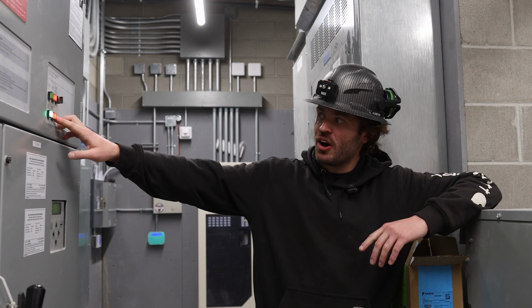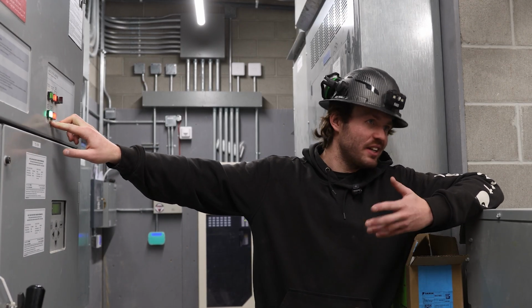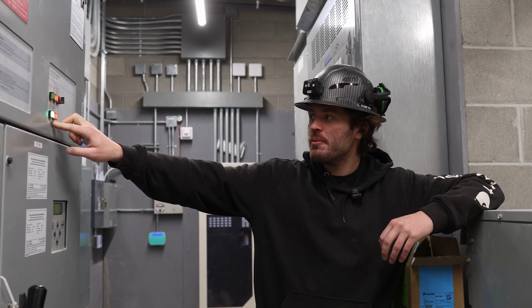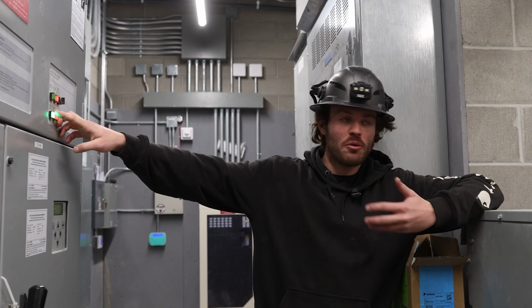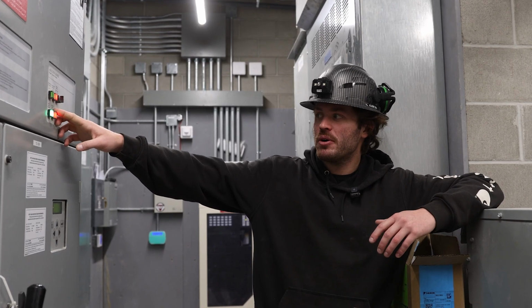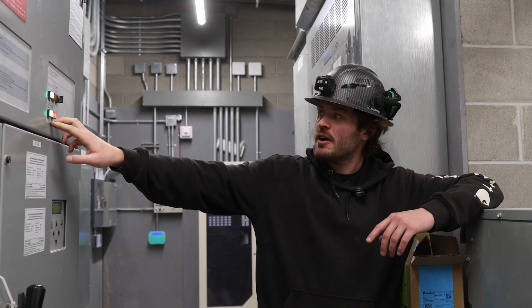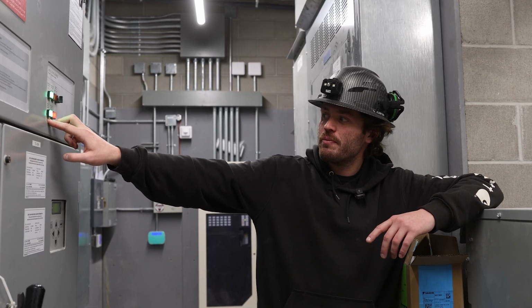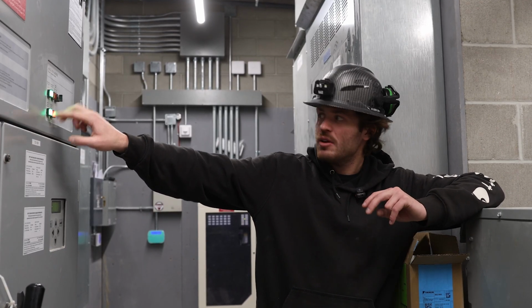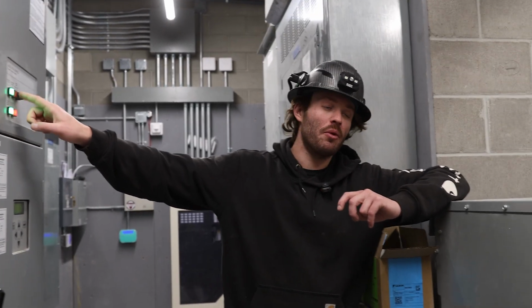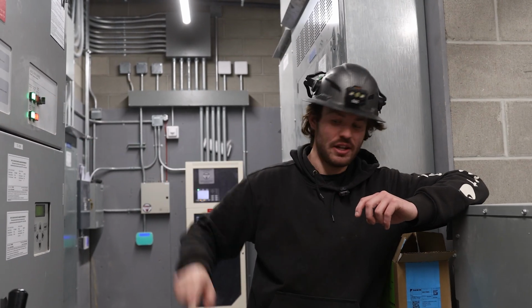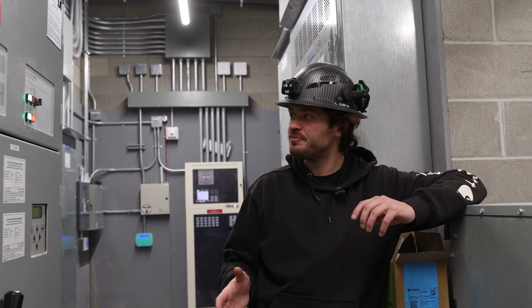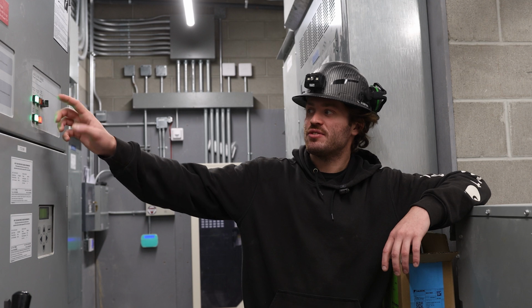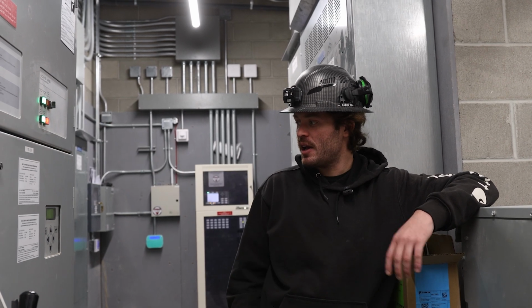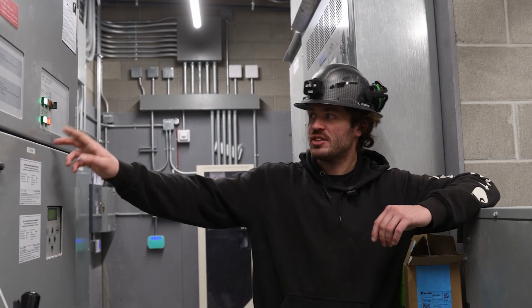The lights up at the top are a quick indication of what's going on. The green ones are normal power, red ones are emergency power. The bottom two show if the source is good. Of the top two, only one will be lit up, showing where our transfer switch is actually in position. So it just transferred back to normal power and our lights switched.